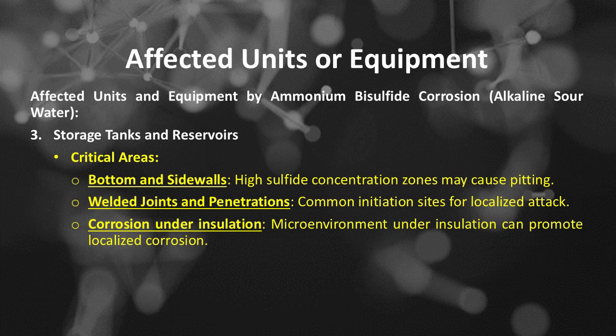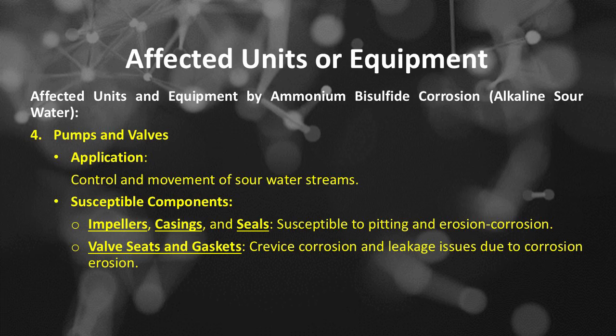High sulfide concentration zones may cause pitting. Welded joints and penetrations are common initiation sites for localized attack. Corrosion under insulation: the microenvironment under insulation can promote localized corrosion. Affected units and equipment by ammonium bisulfide corrosion or alkaline sour water.